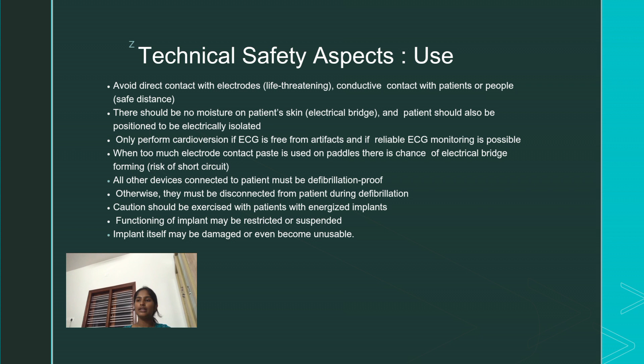When too much electrode contact paste is used on the paddles, there is a chance of an electrical bridge forming. All other devices connected to the patient must be defibrillator proof, otherwise they must be disconnected from the patient during defibrillation. Caution should be exercised with patients with energized implants. Functioning of implants can be restricted or suspended. The implants themselves may be damaged or even become unusable.